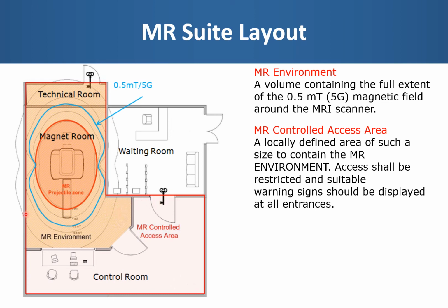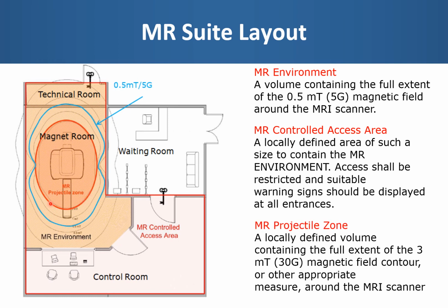And then there is also defined a projectile zone, which is the volume containing the full extent of the 3 millitesla or 30 Gauss magnetic field contour around the scanner. This is the field at which you would start to expect a ferromagnetic object to have some force of attraction or torque. However, only certain equipment that is deemed MR safe or MR conditional, with the specific conditions stated, are allowed inside the MR environment.